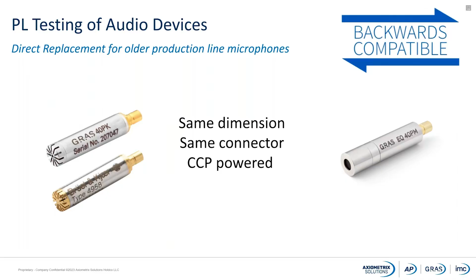Now let's talk about this EQset technology. We consider this a revolutionary technology from GRAS, which is going to be a game changer for all production lines out there requiring microphones for the tests. This is a patent pending technology. The concept is that we keep a 100% analog sensor, but with built-in electronics that will allow for the correction of both the gain, that will be the sensitivity of the microphone, but also the frequency response using an equalizer.